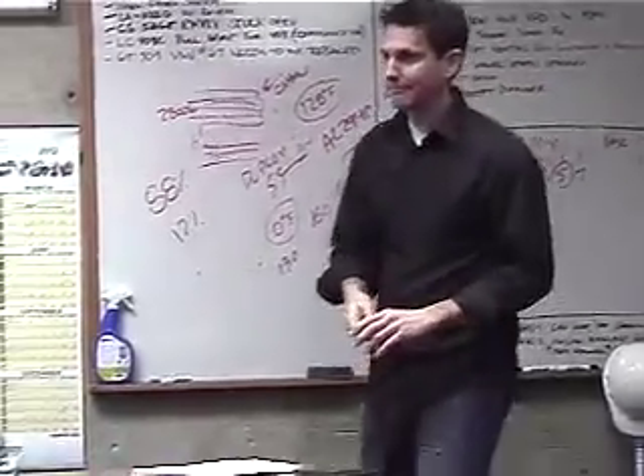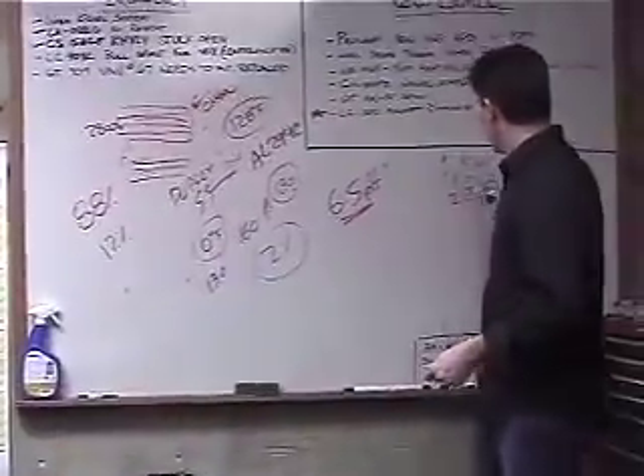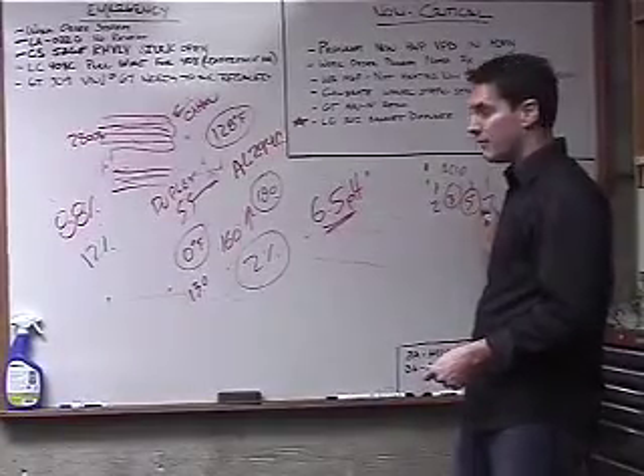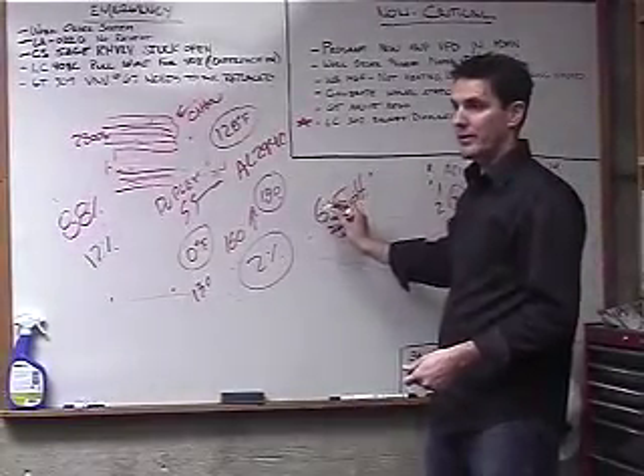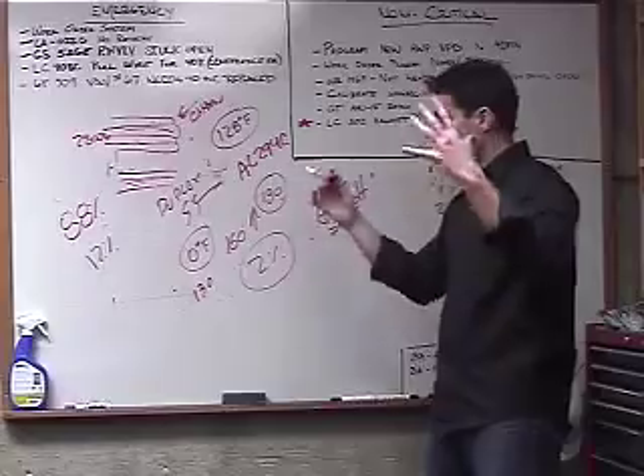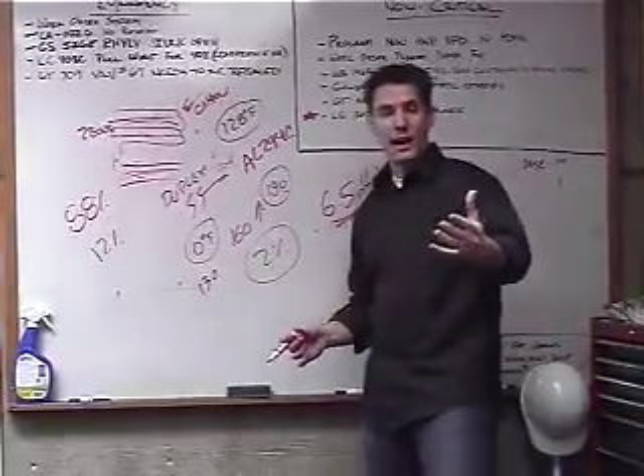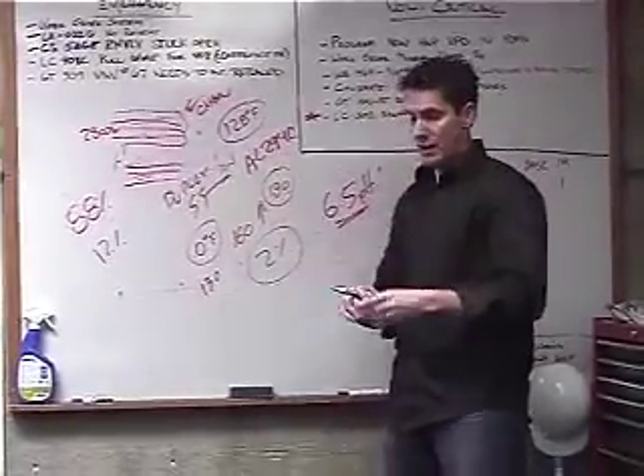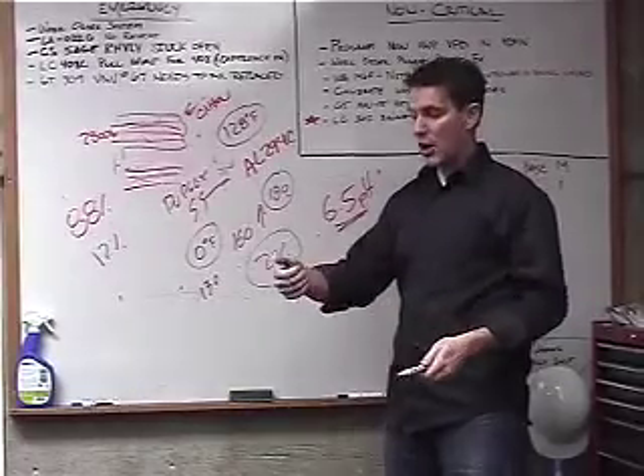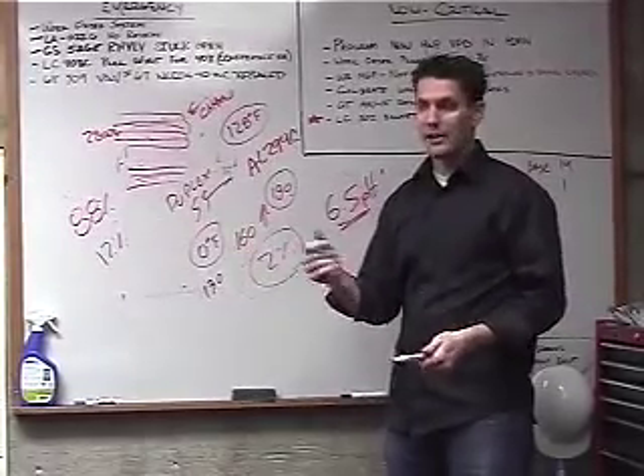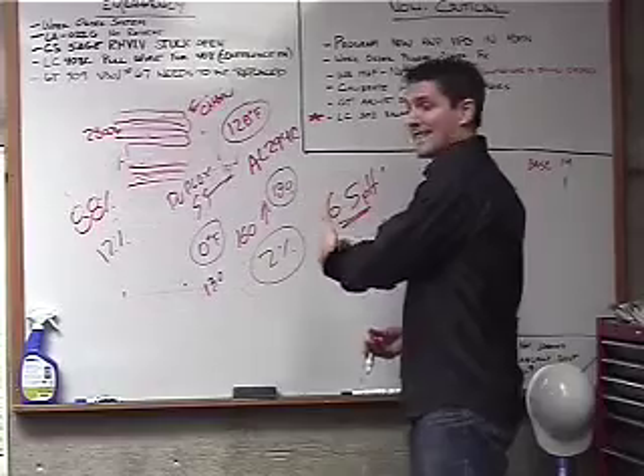Yeah. So what do you do with the water, with the acid drain? Yeah. Okay. So somehow you've got to take this 3 or this 5 and get it back up to 6.5. Again, if you don't, the more condensate that you have, where you guys are coming back with 90 degree water, potentially you're going to have, if you go back there and look, you'll see like a hose being left on, just water continually draining out. Okay? That's an acid draining out.